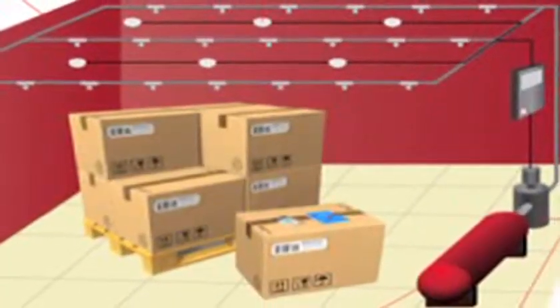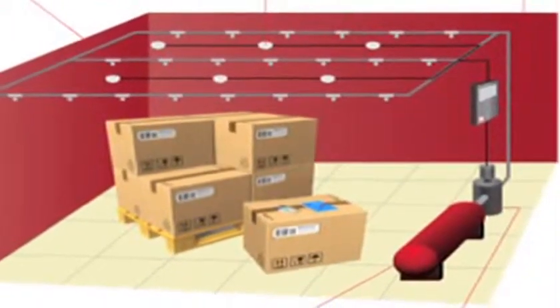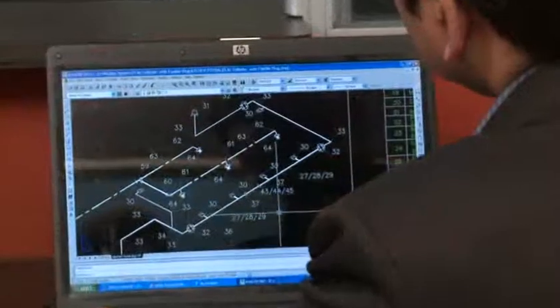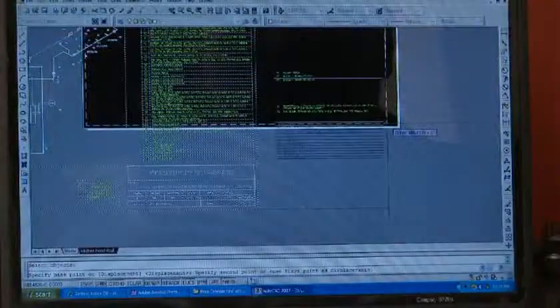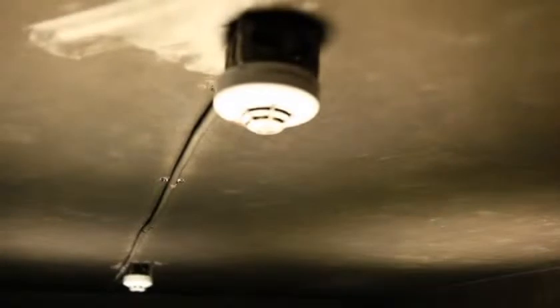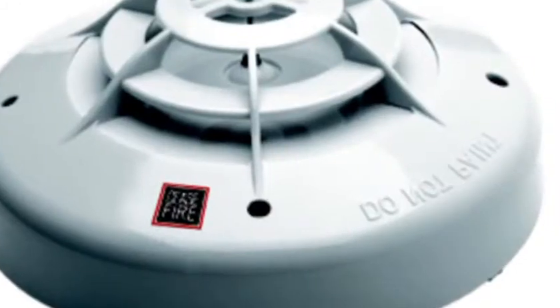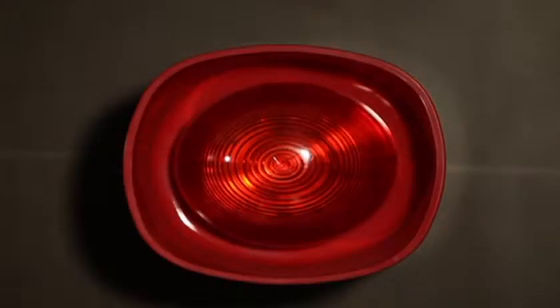The Auto-Quell system has been set up according to design provided by the Ceasefire Design Cell, which studies the needs and vulnerabilities of the area at length. Do keep in mind that the setup may differ as per variations of applications. Detectors in this system include either smoke, heat and rate of rise and beam detectors, or a combination of these. The audible alarm goes off as soon as the fire is detected, alerting personnel in the area to the danger.